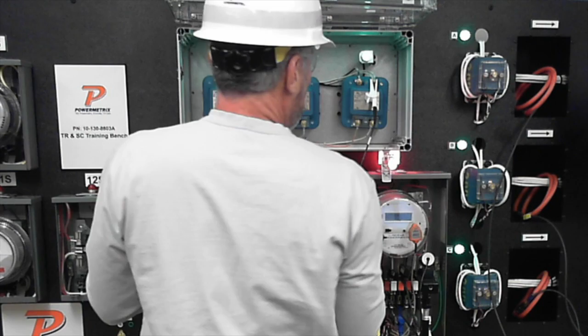So that's what you'll do here with your 3 phases. I'll connect these 3 phases right here, then come up and make a connection very similar to the one on the CTs. I come over here first, and since these are tied together, I make my initial connection for my returns. Then I come over here on my H1s on the high side, and go A, B, and C — connecting on my high sides, because we're dealing with primary here. It is 600 volts or less, but it's still primary for us. Then I come over on my H1 and H2 — I'm on one of my H2s since they're tied together, so I've got H1, H2, H2, red, yellow, blue, HHH. So I'm staying on the high side on that.